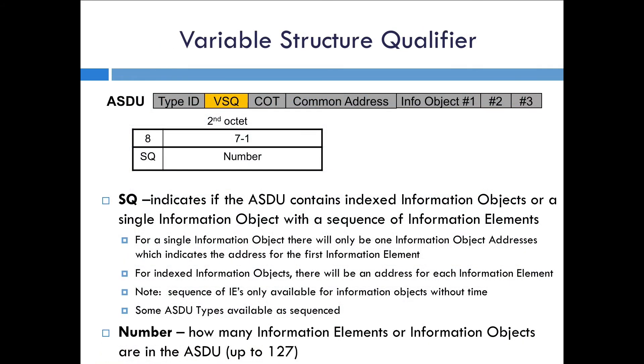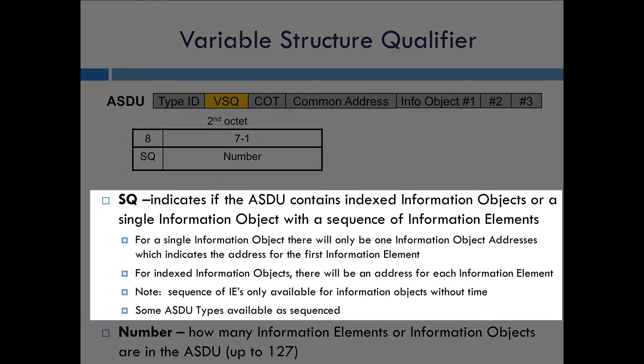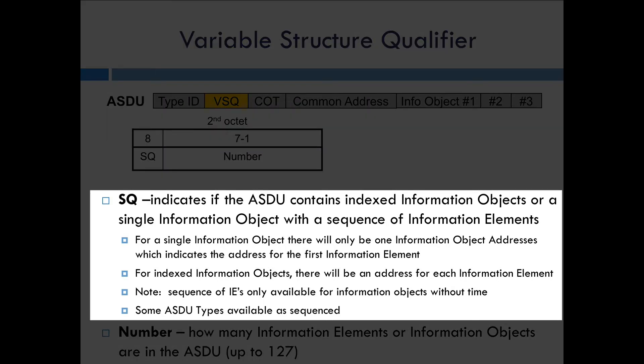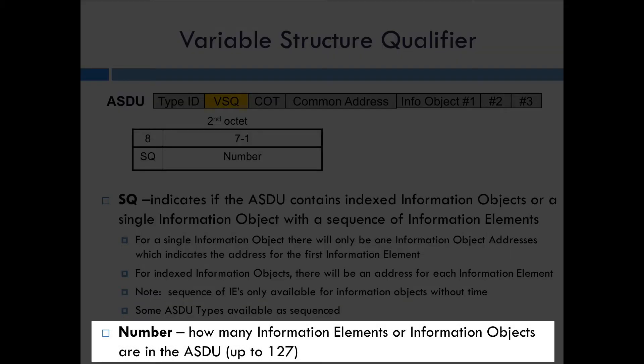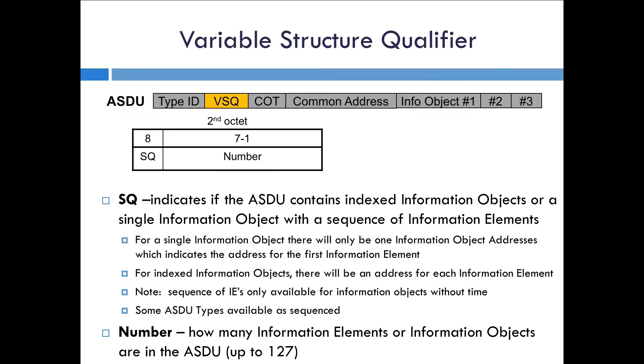The second octet in the ASDU is the variable structure qualifier, which tells you how many elements are in the ASDU. There is an option to have a sequence ASDU — if it's a sequence, the address tells you what the starting element is, and this number tells you how many elements from that starting point are included. If it's not sequenced, the number is simply how many objects you have, and each one will have its own address. The standard tells you ASDU by ASDU whether or not it supports sequence data.